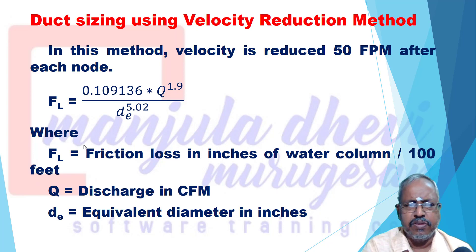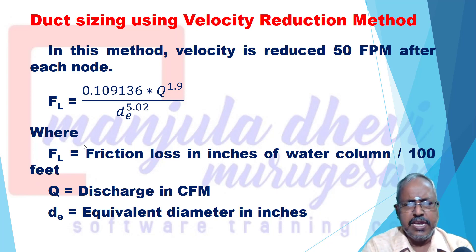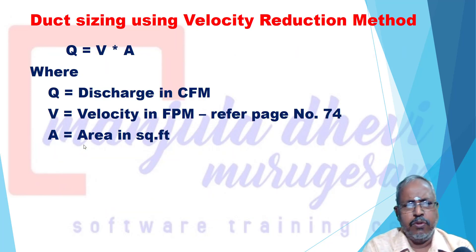The friction loss formula is: FL = 0.109136 × Q^1.9 / DE^5.02, where FL is friction loss in inches of water column per 100 feet, Q is discharge in CFM, and DE is equivalent diameter in inches. Also, Q = V × A, where V is velocity in FPM and A is area in square feet.